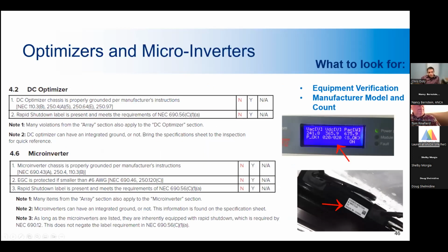All right, so moving on from the array, the next thing down the line is the optimizer or the microinverters. A DC optimizer is essentially a DC to DC converter that takes whatever amperage and voltage is produced at the solar panels and converts it to the voltage and amperage required by the string inverter. Microinverters are essentially an inverter on each solar panel, so all the wire runs coming out of them contain AC electricity as opposed to DC. Then bringing all that together is an AC combiner panel.